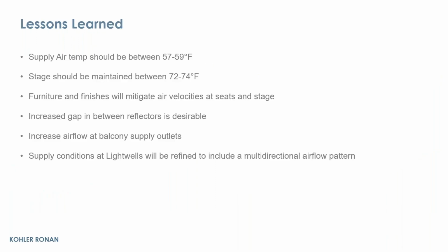For our design and for the acoustical design, we were informed that if we can increase the gap between the reflectors and the acoustical baffles, it is a little bit more desirable, so that there's no pressure created between those gaps. We've increased the airflow at the balcony supply outlets, so that was really good.